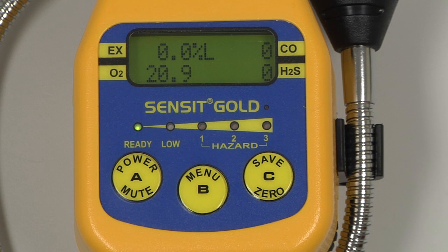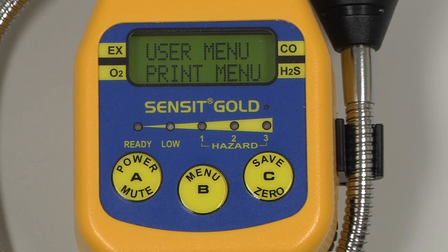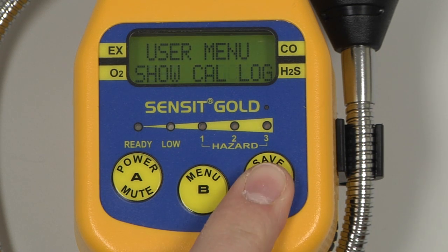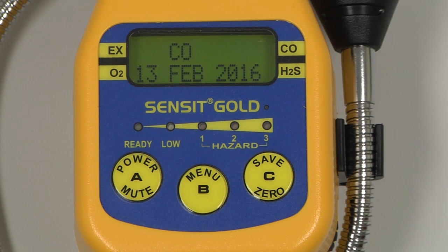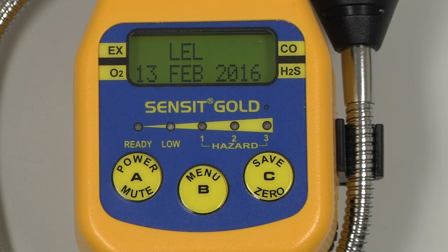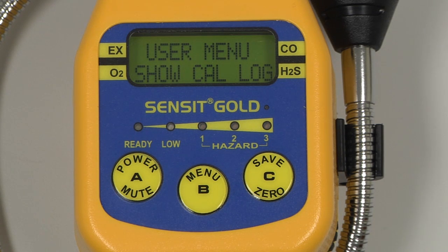To verify the calibration date, enter the user menu by pressing and holding the B button. Scroll through the menu by pressing and releasing the C button until Show Cal Log appears. Select by pressing and releasing the B button. On the display, we will have the sensor and the most recent calibration date for that sensor. We can scroll through with the C button and we will see CO, H2S, and LEL for this case. Pressing and releasing again, we return back to the user menu and can return to the working display by pressing and releasing the A button.